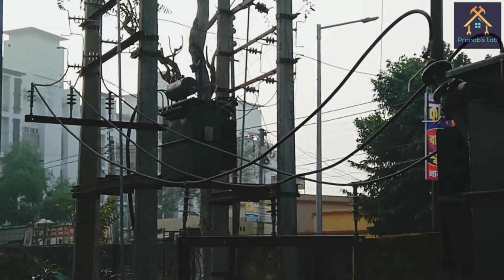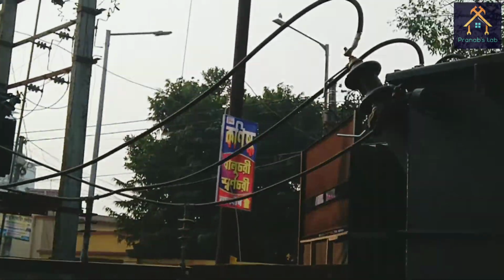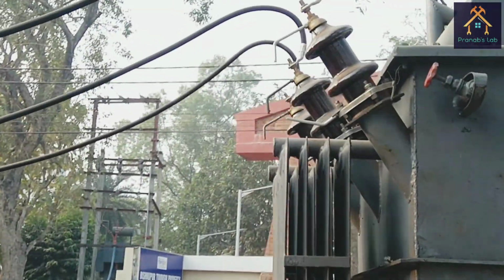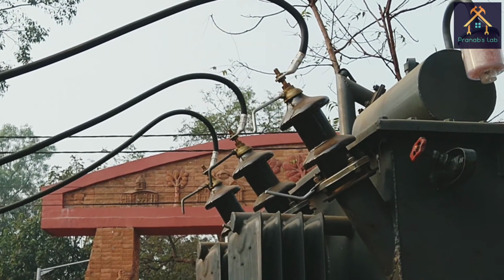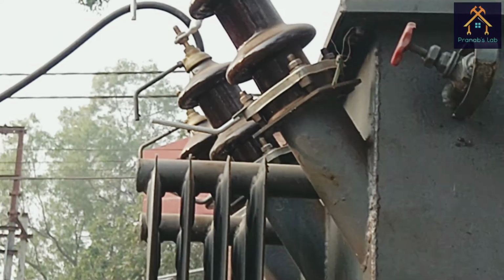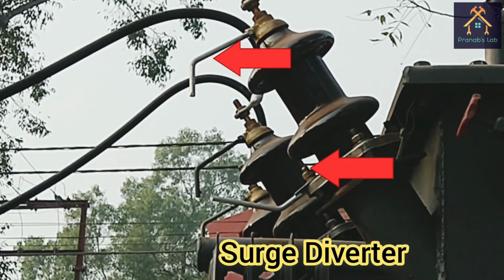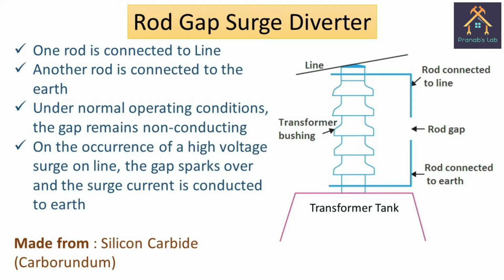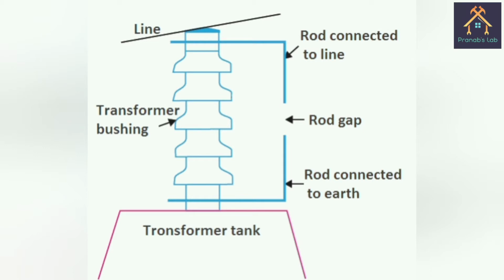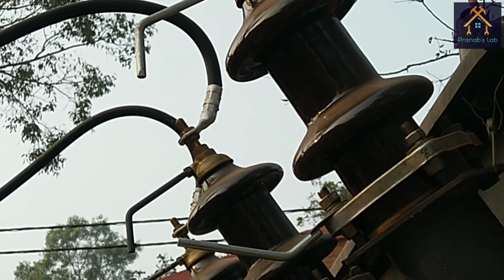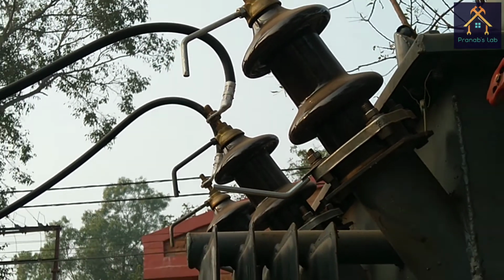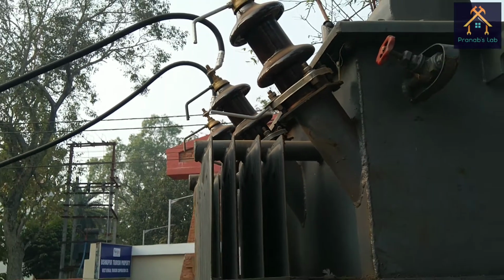You can see the 3 lines coming from the 11 kV feeder are directly connected with another 150 kVA transformer, and there are 2 bent metallic rods placed face to face each other on the high tension bushing, and this is called the rod gap surge diverter. One rod is to be connected with the line and another is to be connected with the earth of the transformer body. Normally the rods are not conducting, and when a lightning surge strikes it, then the high voltage surge breaks down the air gap between the 2 rods and conducts to ground. Thus the whole transformer is protected from the lightning discharge. The distance between the gap and insulator should not be less than 1/3 of the gap length.